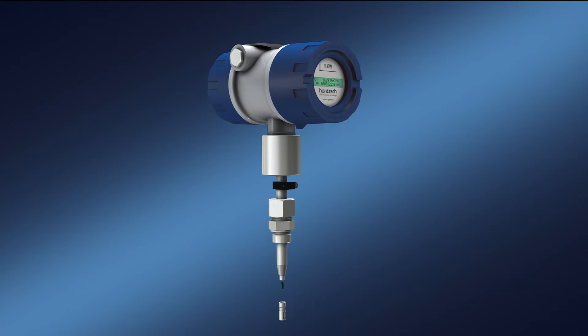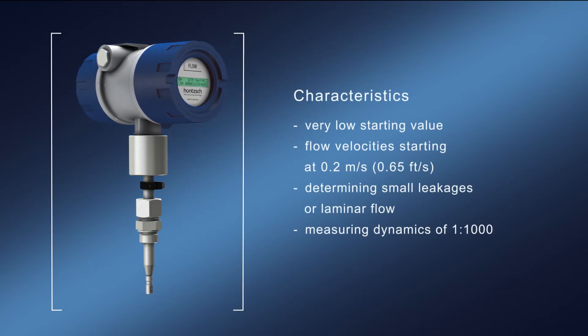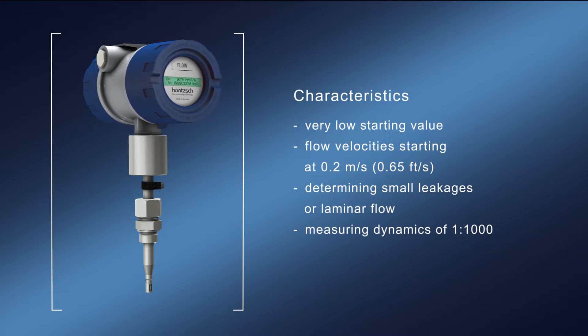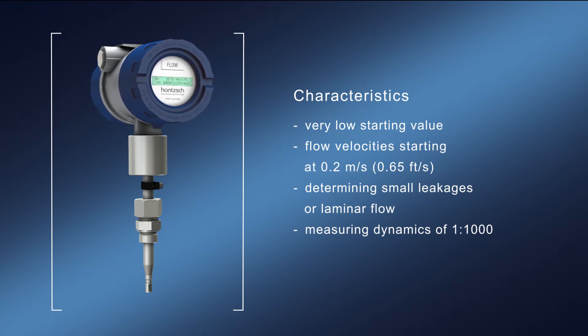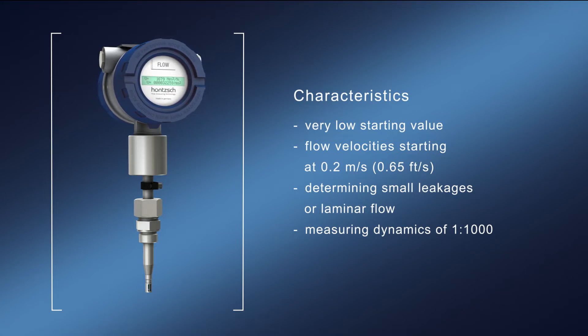The sensor's very low starting value makes it suitable for lowest flow velocities starting at 0.2 meters per second and is therefore ideal for determining leakages and laminar flows. Exceptional! Despite the low starting value, the sensor has a measuring dynamic of 1 to 1000 and therefore delivers exact measuring values in every application.